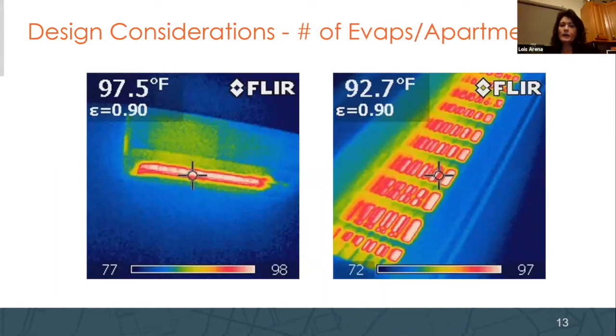These are infrared images of the units at the house at Cornell Tech, right? So this is a heat pump only system. This is one apartment that had a wall mounted unit and a floor. Most of them had floor mounted units. Neither of these rooms are calling for heat right now. And yet you can see the refrigerant charge in the line is making the unit put out about 92, 93 degree temperature. So obviously the building is warmer than 68 degrees set point, right? All of that heat is just loading up into the spaces.